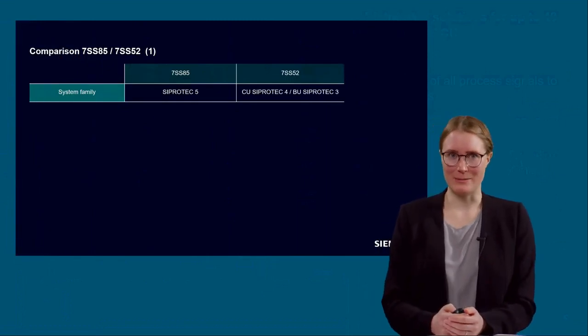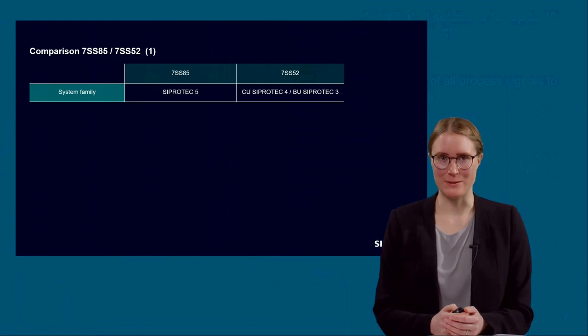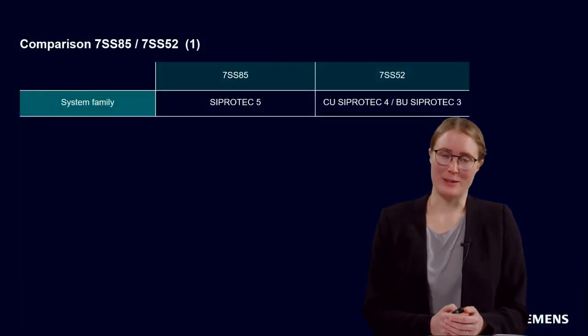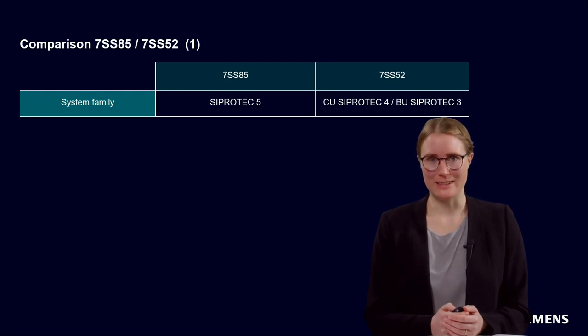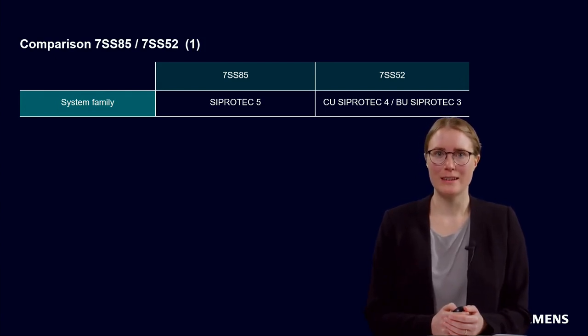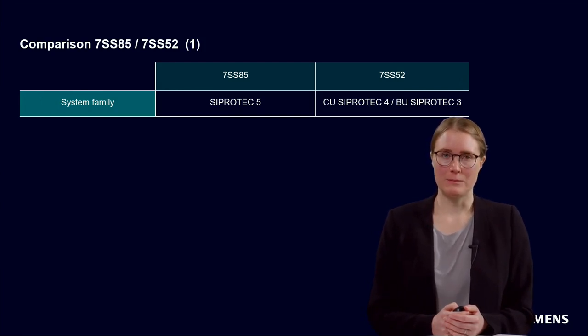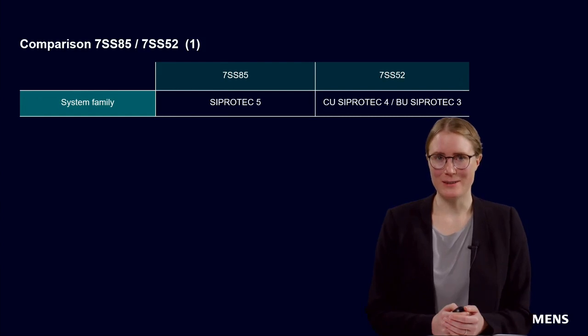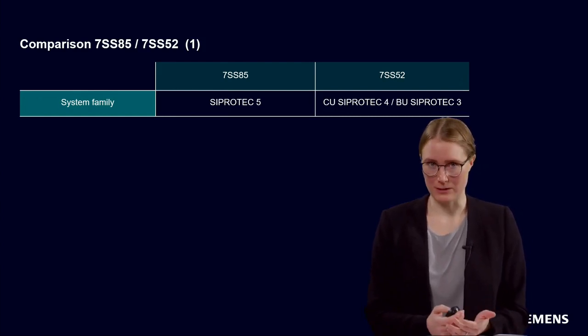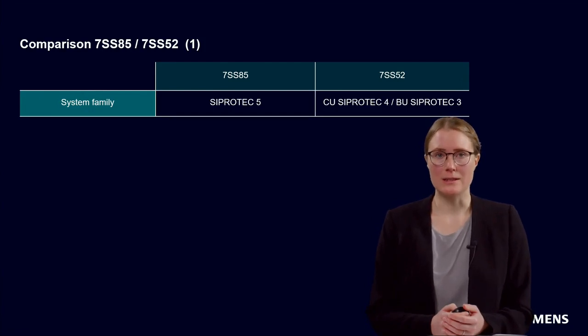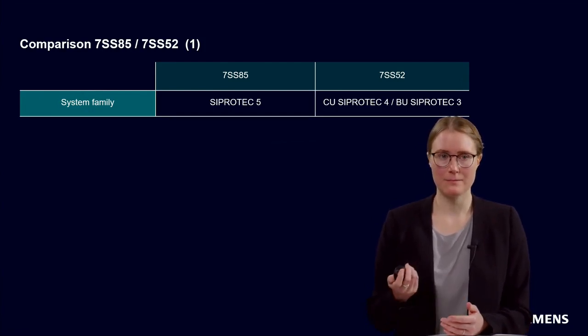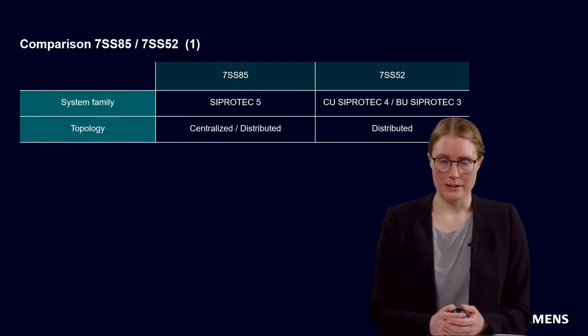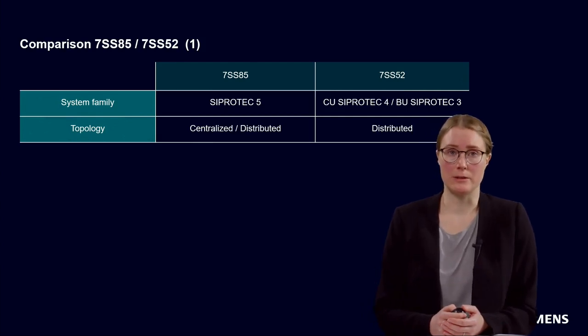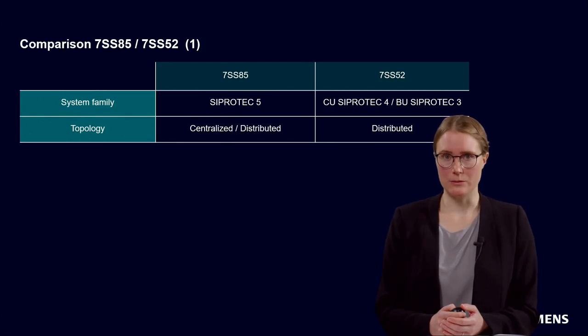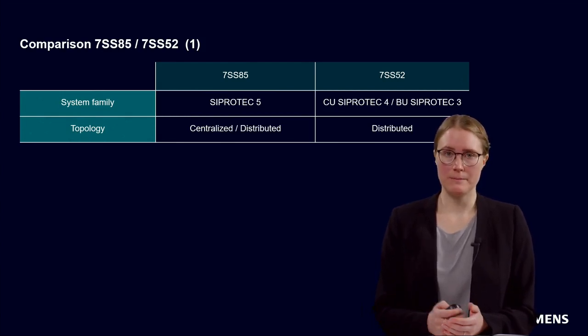Okay. In the next 2 slides, I want to compare our SIPROTEC 4 solution 7SS52 with the SIPROTEC 5 solution 7SS85. In the system family, the 7SS85 is fully integrated in the SIPROTEC 5 platform. With the 7SS52, the central unit is a SIPROTEC 4 front end, specially designed for busbar protection. The bay unit is a SIPROTEC 3 device. The topology in the 7SS85 can be a centralized setup, distributed setup, or even a mix of both variants. With the 7SS52, it is always a distributed setup.